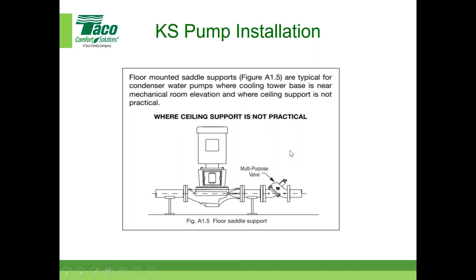Here's one with the stand - you can put the stand on a pad or directly onto an isolation pad. The pump should not be rigidly attached or welded to the base pad structure unless flexible couplings are used, since it needs to be able to move. Make sure that's in your specifications, or on your walkthrough, you understand that before approving the project or signing off.